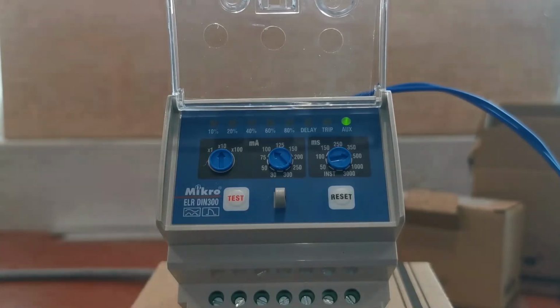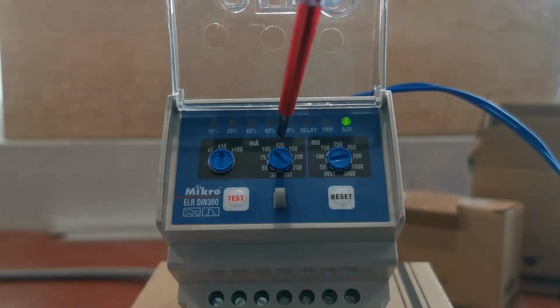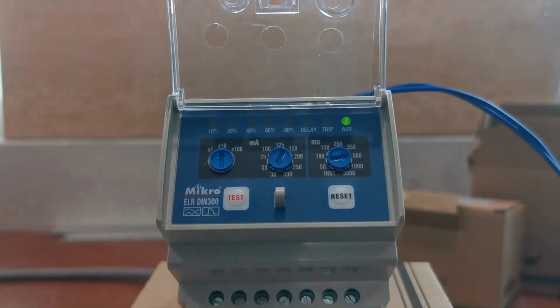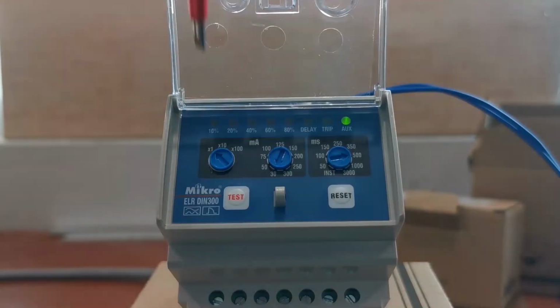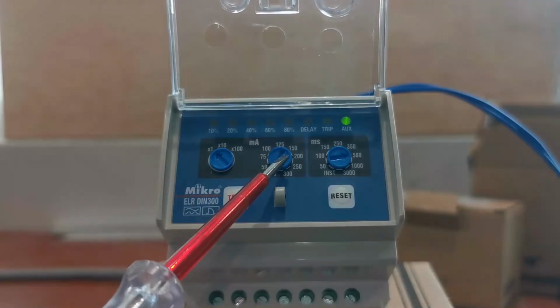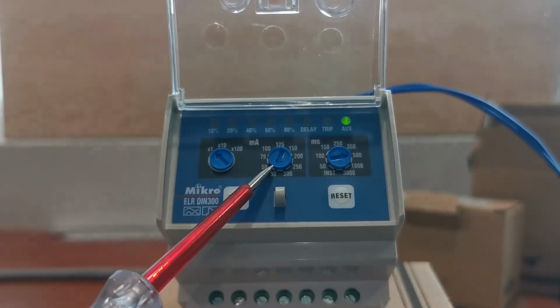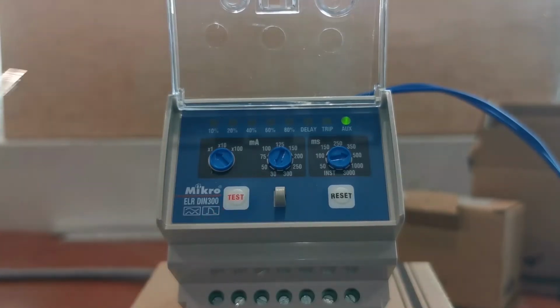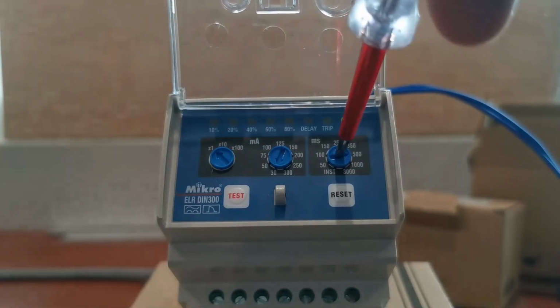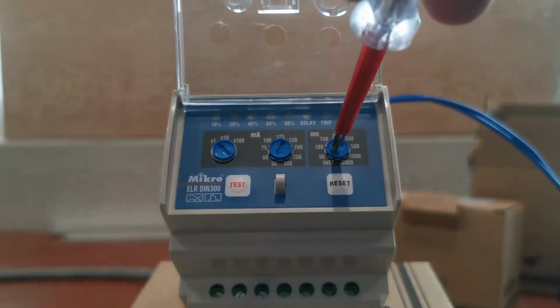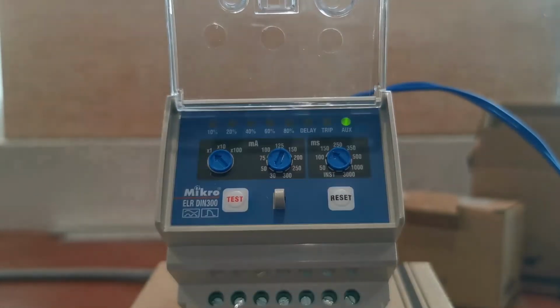Now I'm going to demonstrate a setting of 30 milliamps and injecting 45 milliamps, which shows that the earth leakage relay will trip. Firstly, I'll set it to 30 milliamps, and the multiplier to 1. Be careful when changing the knob. Make sure it doesn't go in between the two settings here. You can hear a distinctive click sound when you reach the correct setting. And the time delay, I'm going to set to 0.15 seconds. Now we're going to inject 45 milliamps to trip the earth leakage relay.